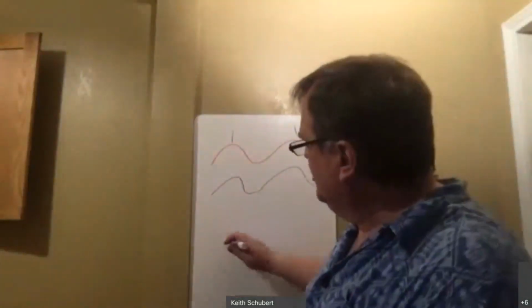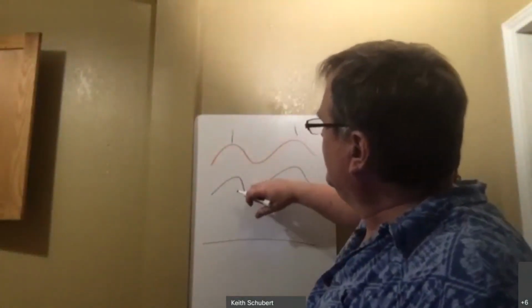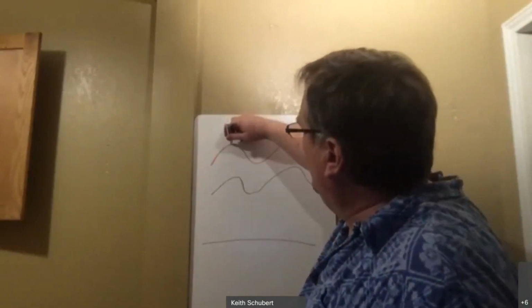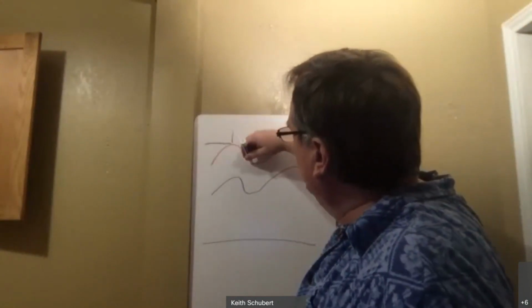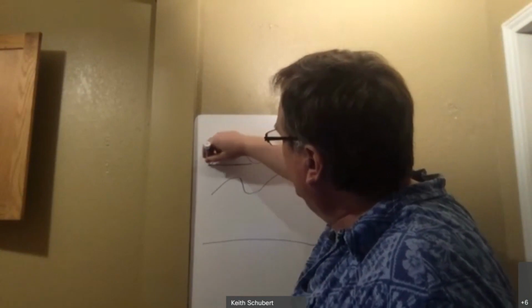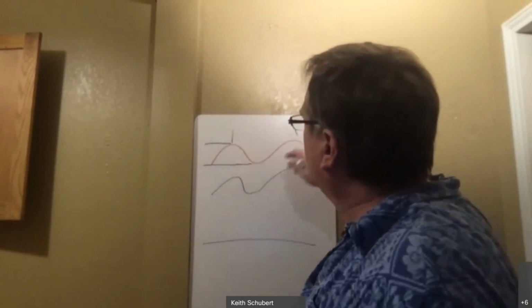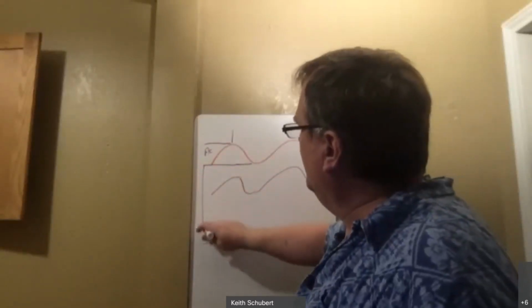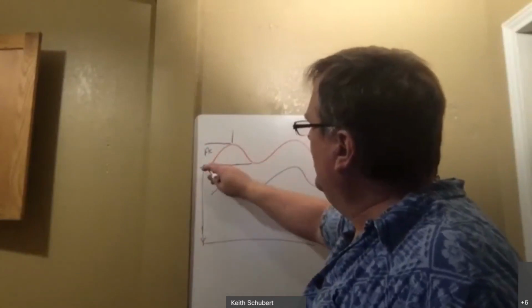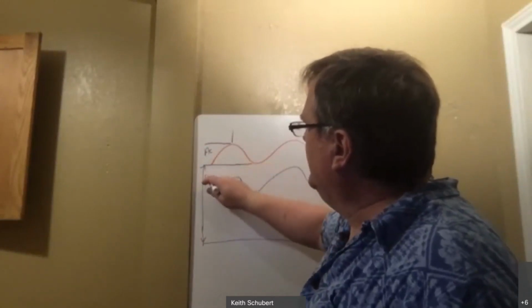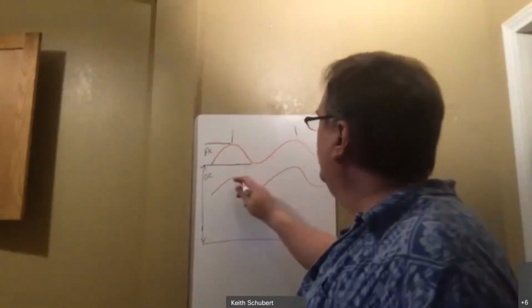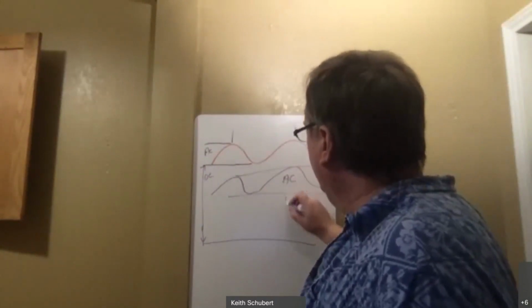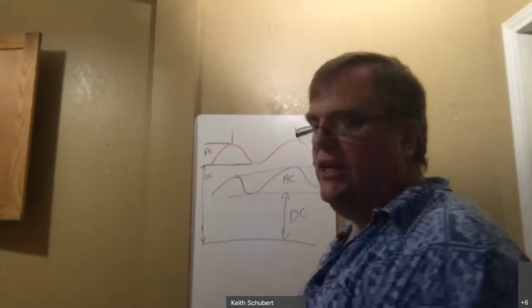When you do the measurement, this is where 0 is, and say this is infrared and that's red. And if you watch all the videos that I've put out, I do have some on SpO2 calculation. We have this range here. What's the min to max on the red? I call this the AC component. And then from the 0 value up to the minimum on red is the DC component for red. And you can do the same thing for the infrared, so you'll get an AC and you'll get a DC.